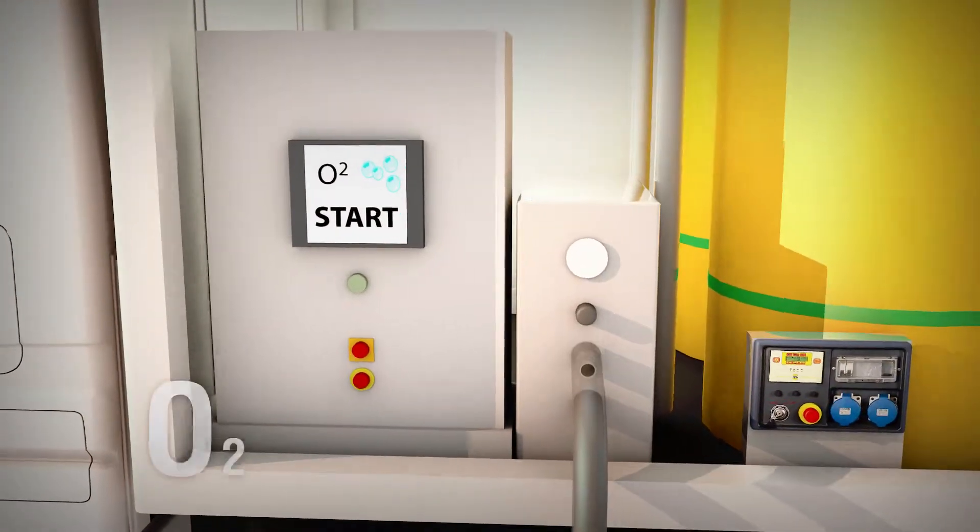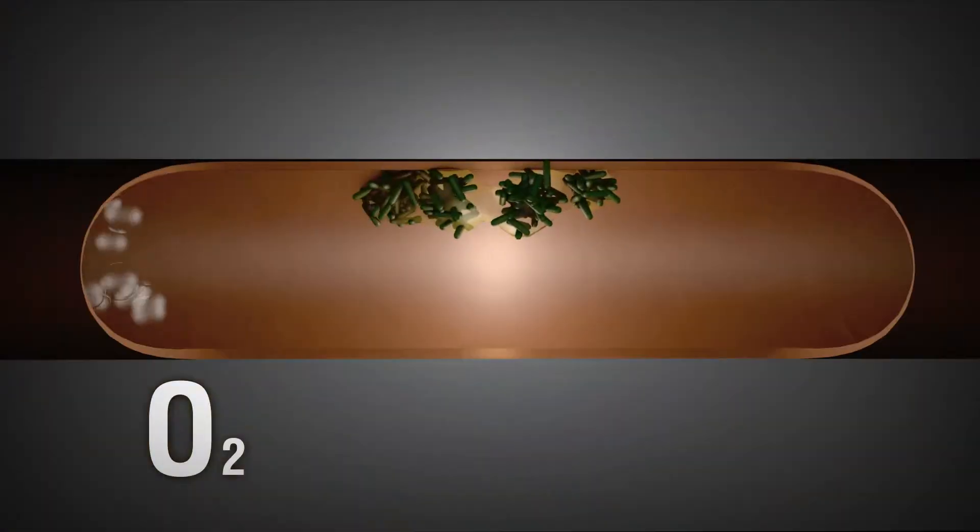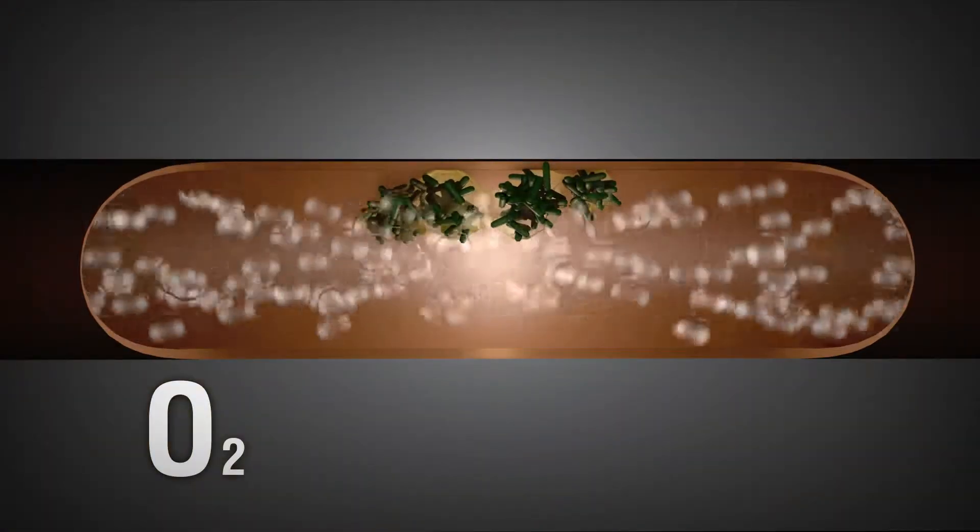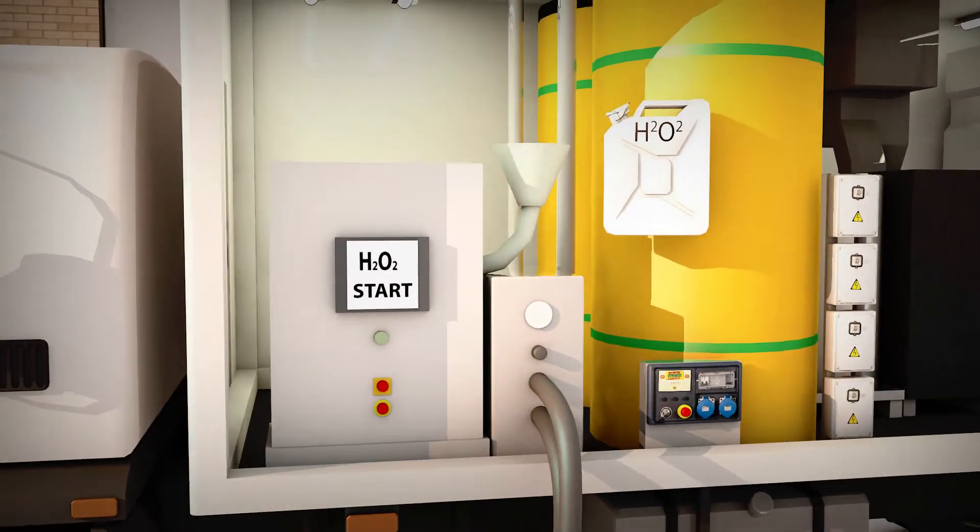Phase 2 involves blowing air pulses through the pipes at 5 second intervals. Together with the hot water, these pulses cause the Legionella and the biofilm to loosen from the inside of the pipes.